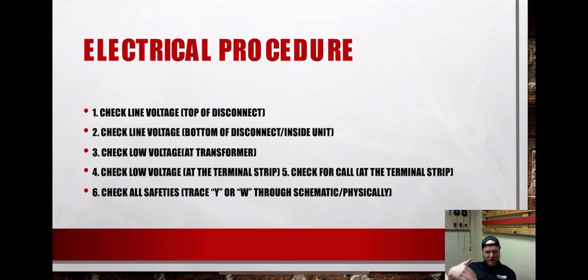Do we have power coming back to the first set of fuses? Do we have power going to the transformer? Do we have it coming out of the low voltage side of our transformer? Do we have power at our terminal strip? Do we have a call for cooling or heating at our terminal strip? And have we checked all of our safeties, tracing Y or W through your schematic and physically?